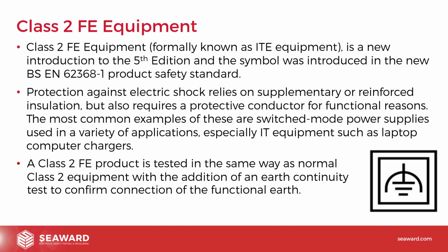However, for functional reasons, there is an earth connection. That's not there as part of the protective measure like it would be with Class 1. It's not protective earthing, it's functional earthing. It's there to make the equipment work. It's there for screening, for bonding, those sorts of things.